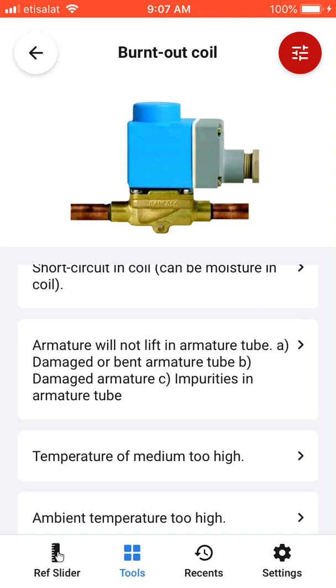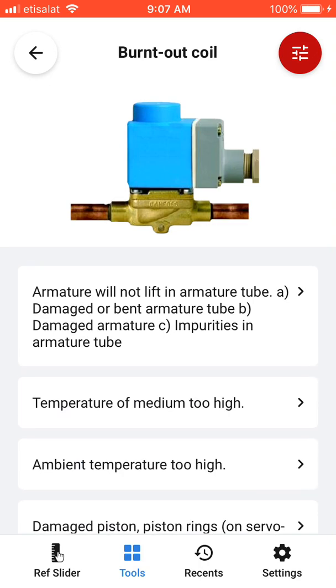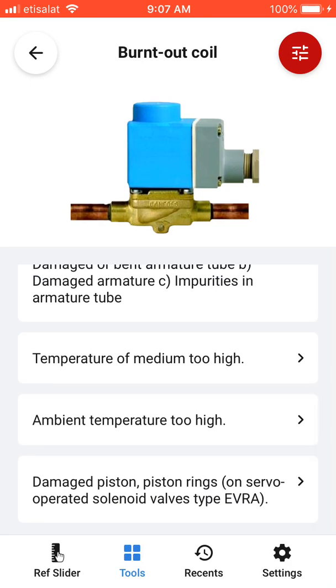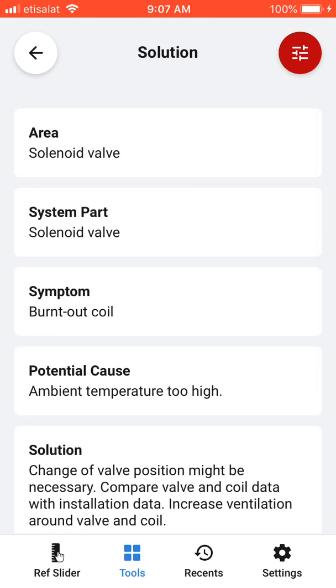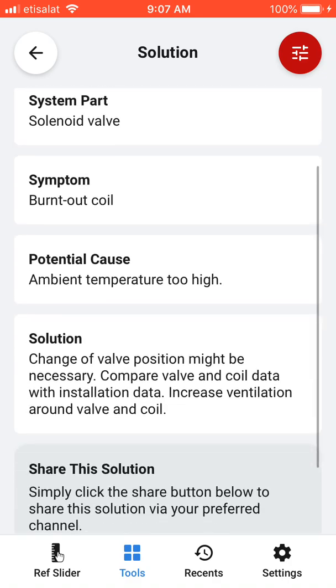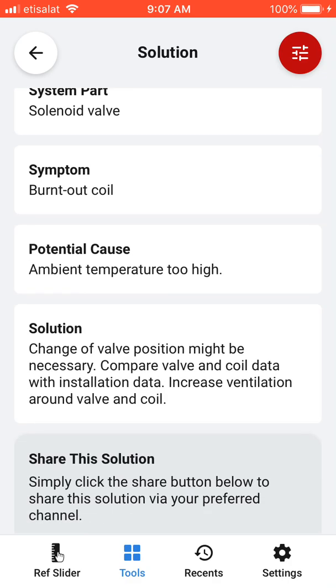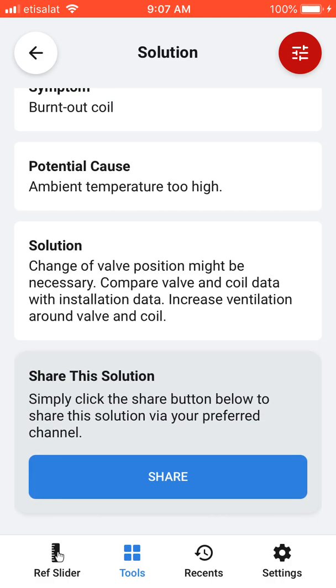The reasons for that fault could be incorrect voltage or short-circuiting of the coil — the armature will not lift. Another cause is medium temperature or ambient temperature too high, or a damaged piston. For example, if the ambient temperature is too high causing this fault, the solution may be to change the valve position, not towards the sun but to the shaded side. You can also share the solution with another technician or engineer.